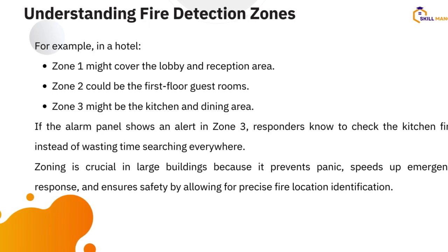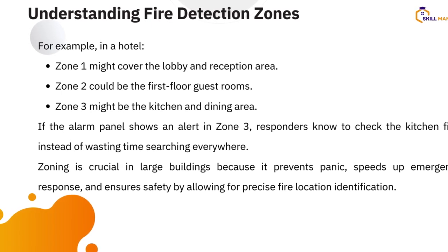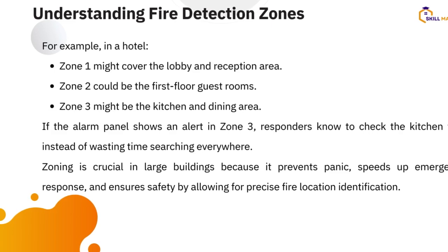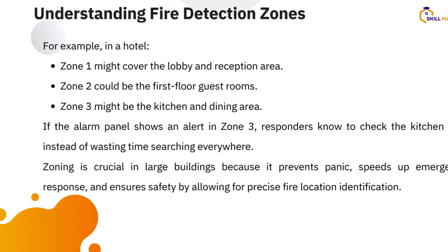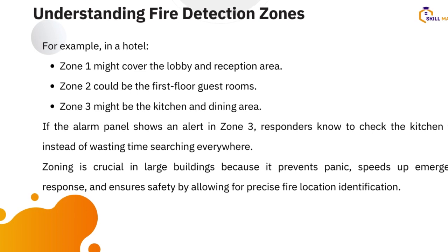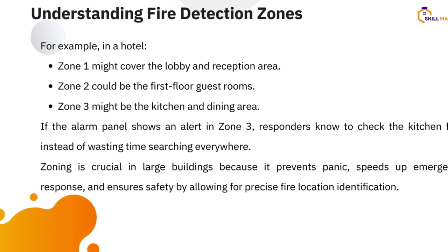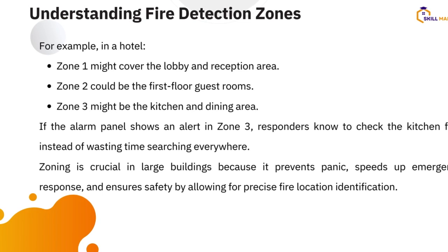You get a building now, a complex, they want you to put fire alarm as an integrator, as an installer, as an expert. You have to zone the building. Oh, this area is close, I'll put it on Zone 1. This other area, they are close to each other, they are nearby, they are easily connected. Zone 2. The next one, Zone 3, Zone 4. So this will advise you the kind of panel you are going to be buying.